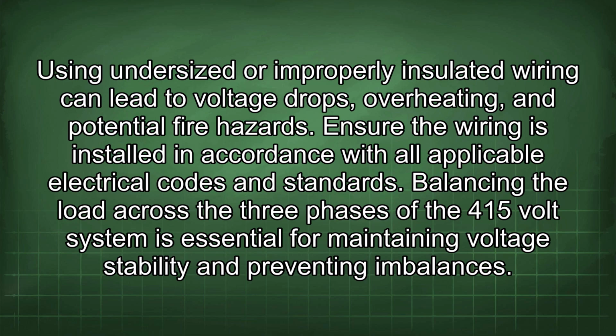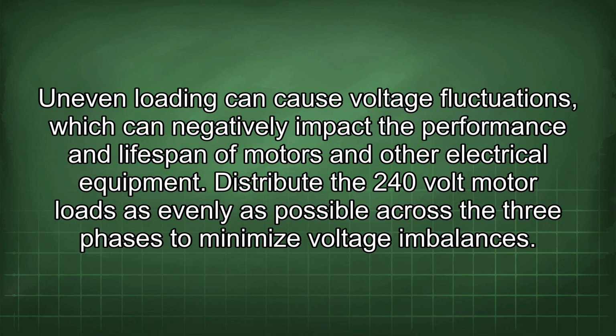Balancing the load across the 3 phases of the 415-volt system is essential for maintaining voltage stability and preventing imbalances. Uneven loading can cause voltage fluctuations, which can negatively impact the performance and lifespan of motors and other electrical equipment. Distribute the 240-volt motor loads as evenly as possible across the 3 phases to minimize voltage imbalances.